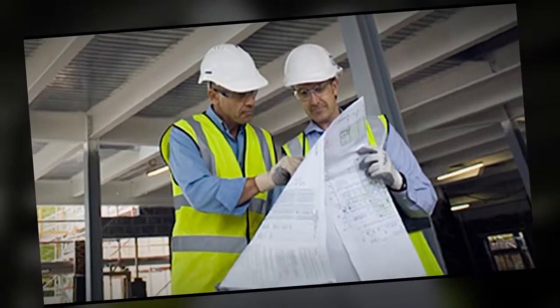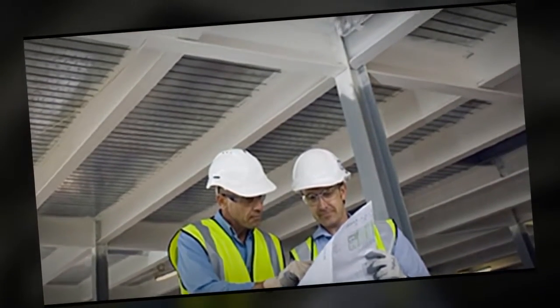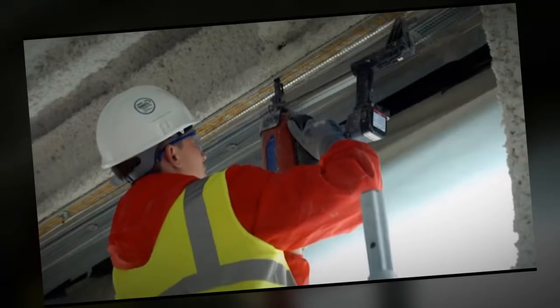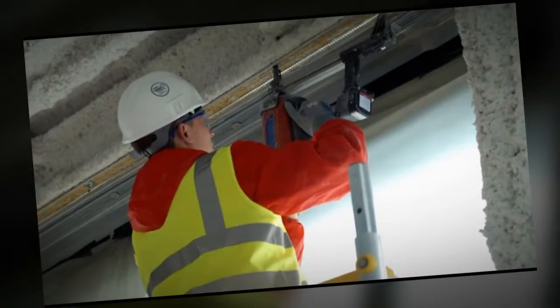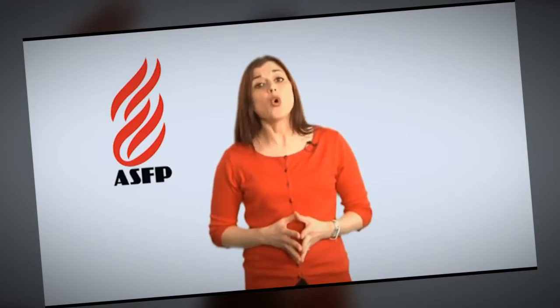Fire risk assessors will normally be unable to undertake a detailed survey of the fire protection to the structural frame of a building. However, they should, while inspecting the other passive fire protection systems, check the passive fire protection to the steelwork for damage or obvious omissions. Any obvious and significant defects may require a full invasive third-party inspection. Again, all checks and outcomes must be recorded for future assessments and inspections.